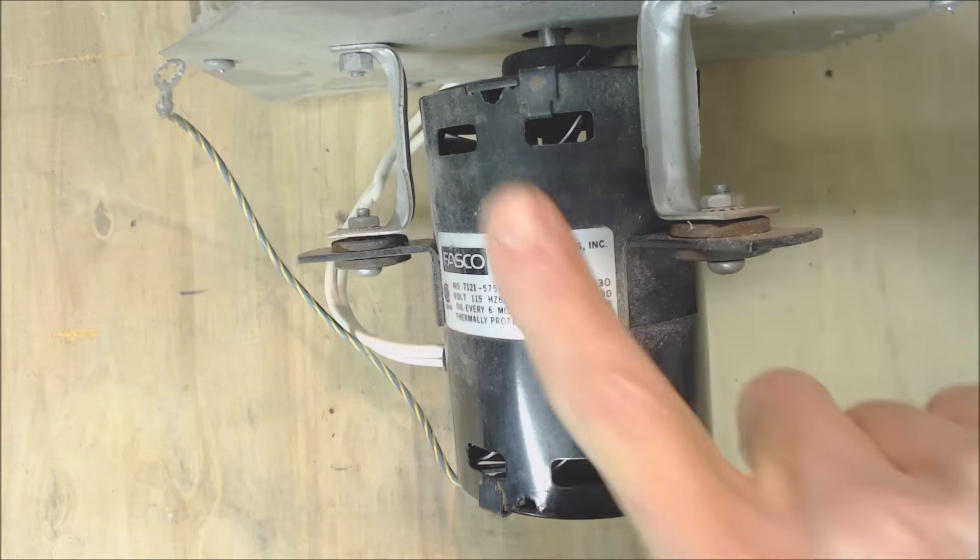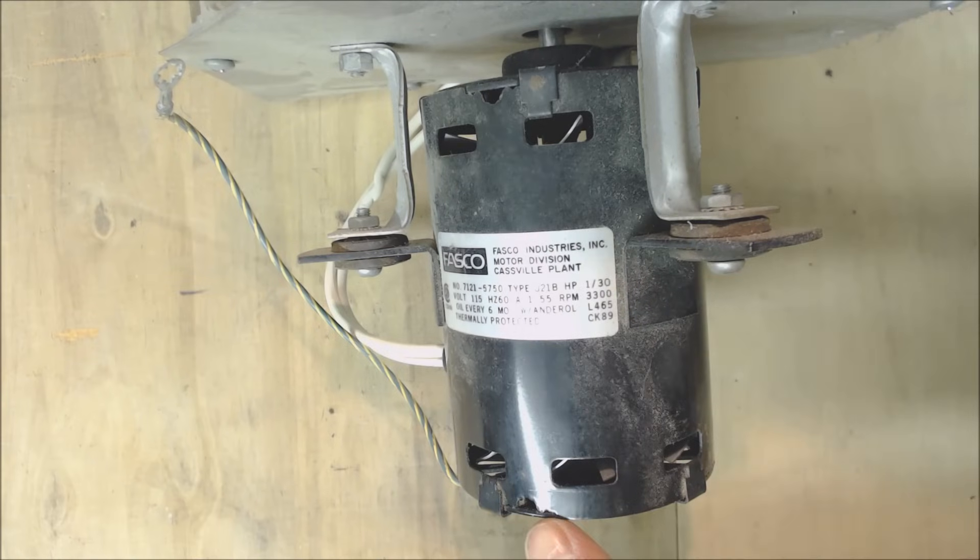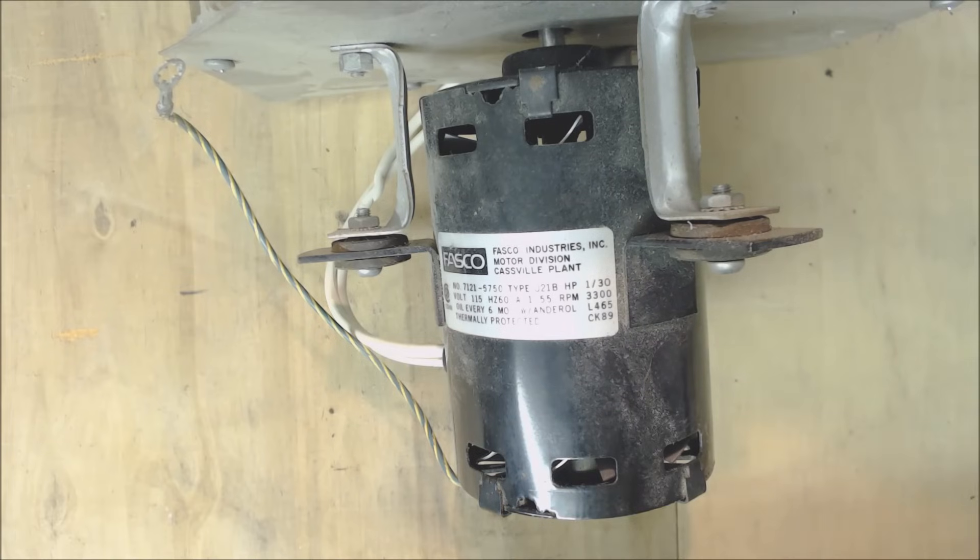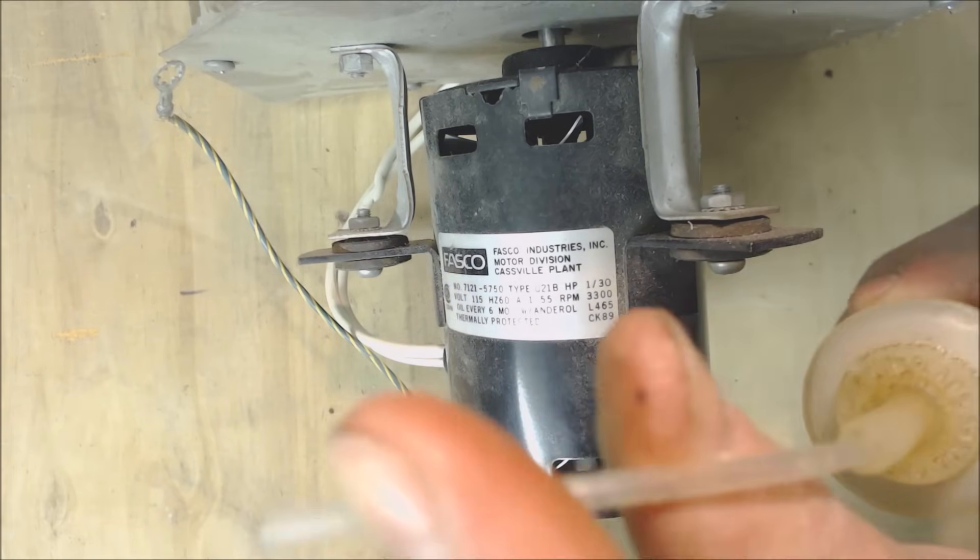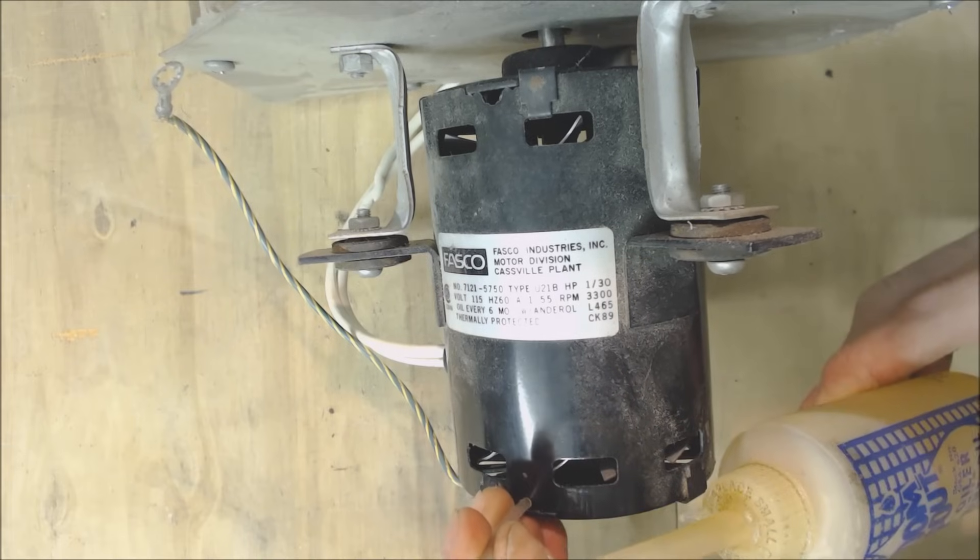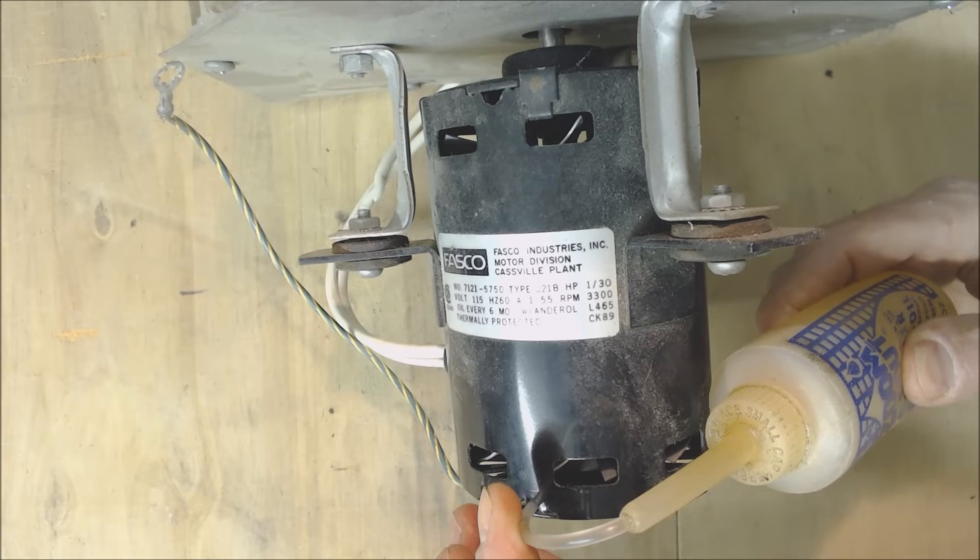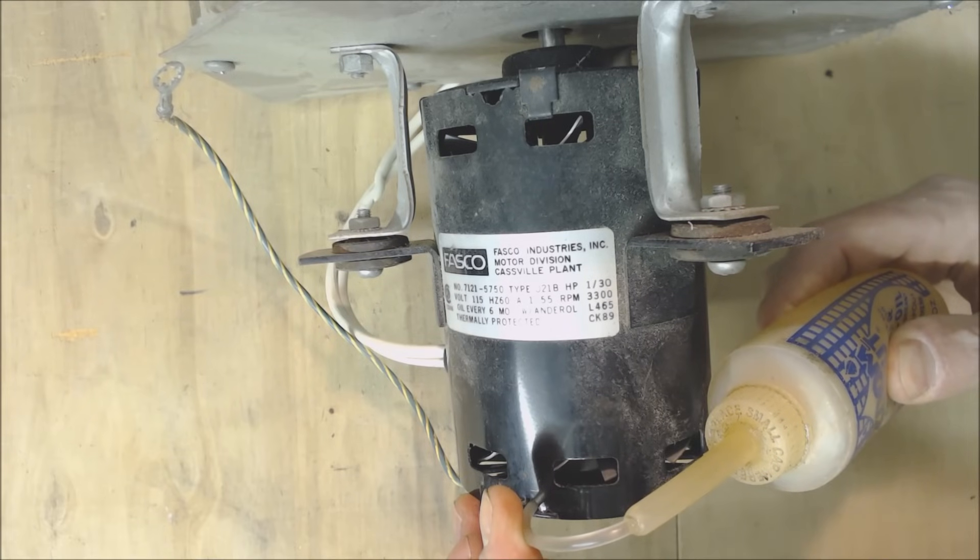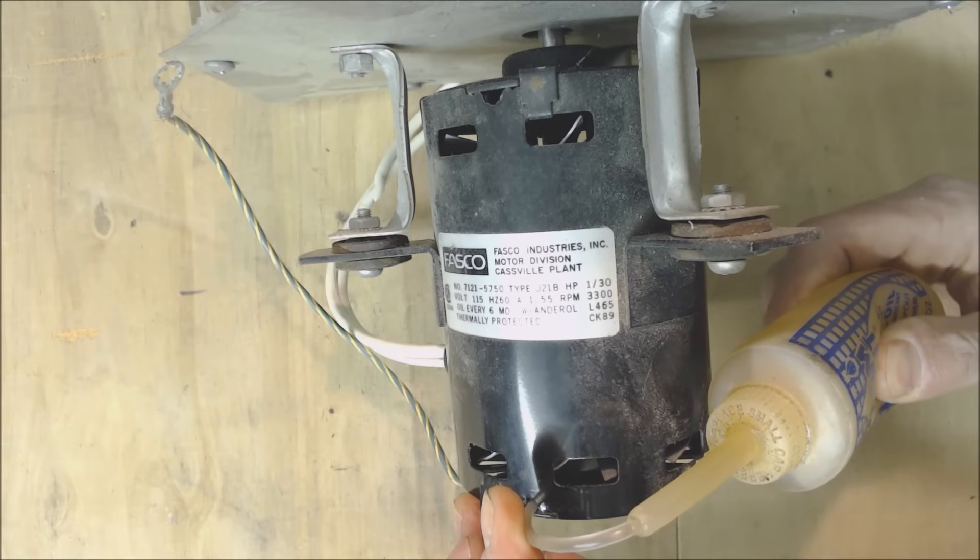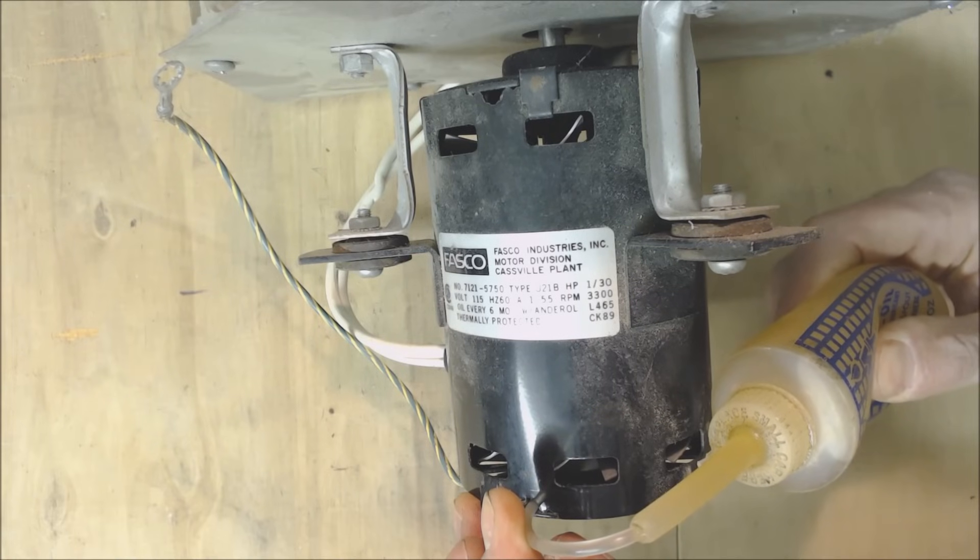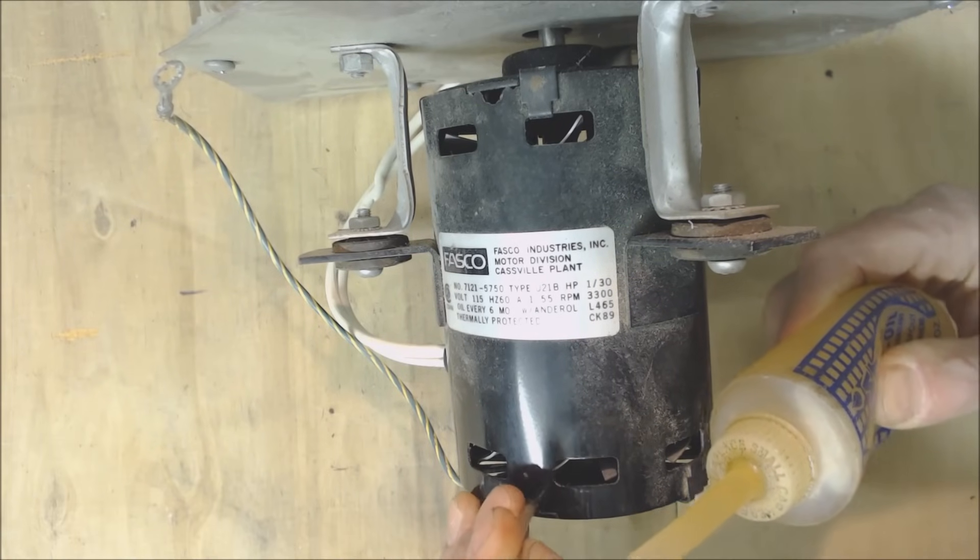If you notice that a motor has actual ports on it for oil, those are not sealed bearings and those are the ones that end up needing to be oiled. If it ran out of oil and the bearings are seized, then the damage has already occurred and that would be one that you would end up recommending replacing. But how you add the oil in is you just go ahead and take this tube right here and you put it right into the hole and then you go ahead and squeeze your zoom spout until you have this basically overflowing. You don't want to overflow crazy amount, but you do want to get enough oil in to make sure that you have that whole reservoir filled up. So we should be pretty darn close right there.